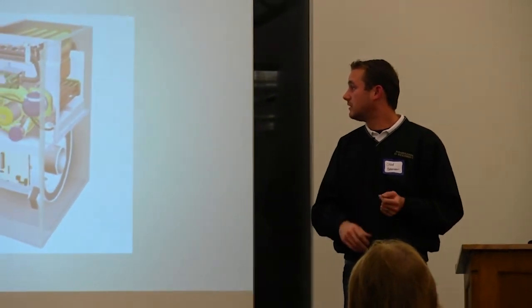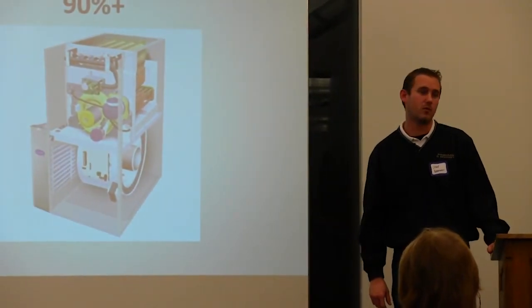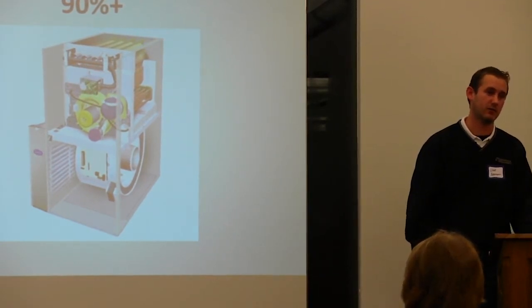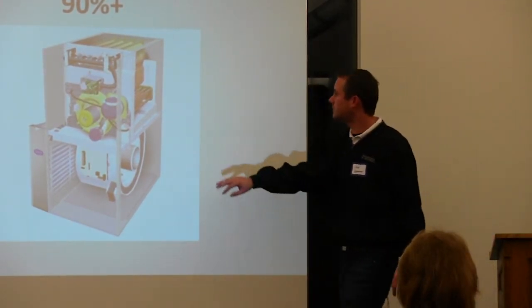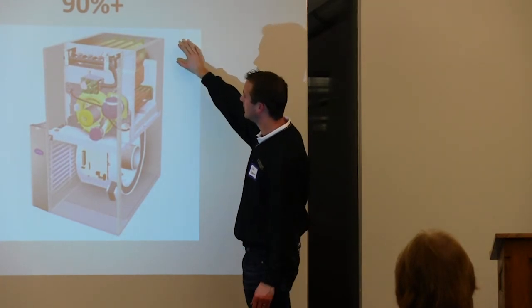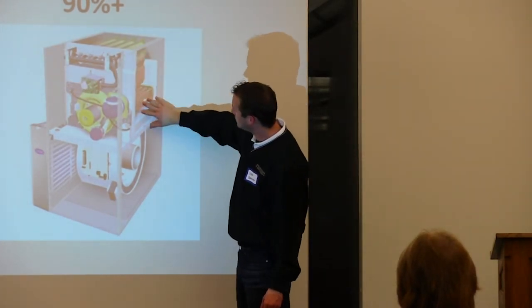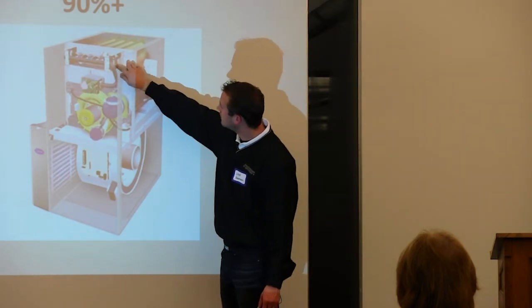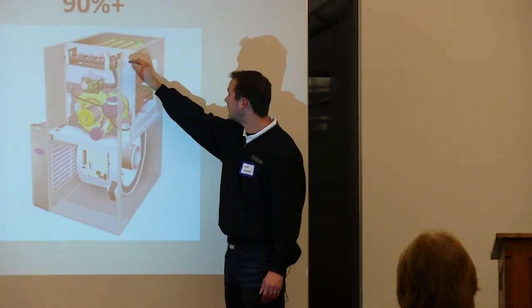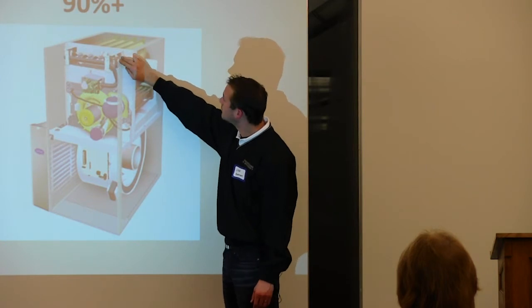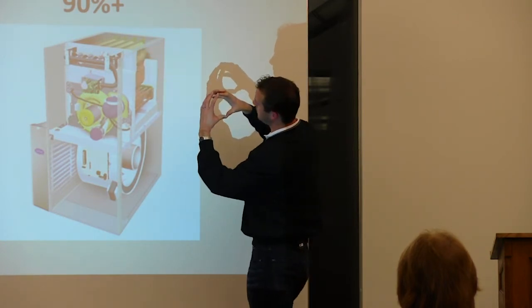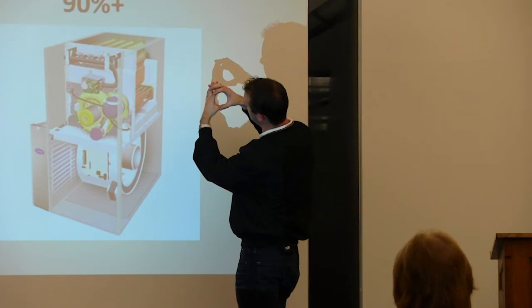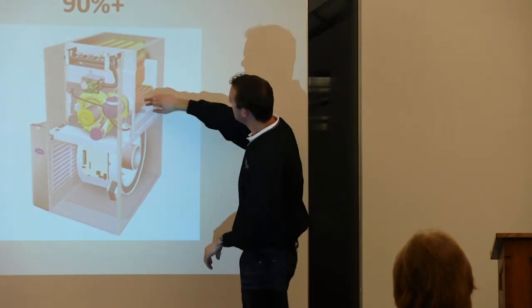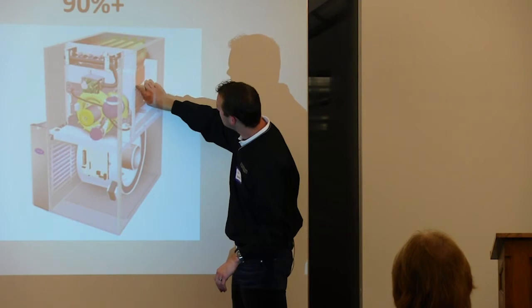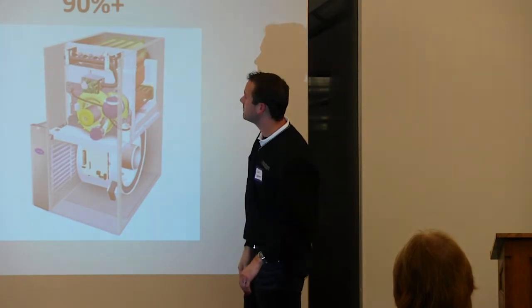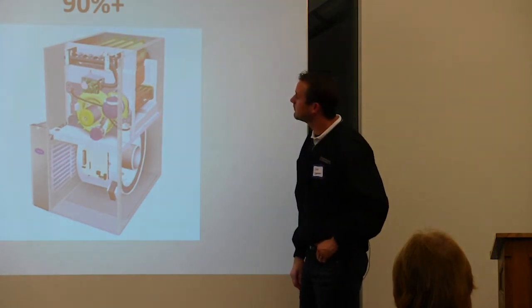The key word there is sealed. You don't want exhaust gases mixing with the air flowing through your house. And so this heat exchanger, what we're seeing in a high efficiency is we have a primary and a secondary heat exchanger. So the exhaust gases, which are burning at 400 to 500 degrees, are traveling through, and this primary heat exchanger is very, very wide open, usually about 1.5 inch tubes. And it's got about 3 bends here, and then you can see it kind of zigzags a little bit. It's restricting that flow as much as possible.